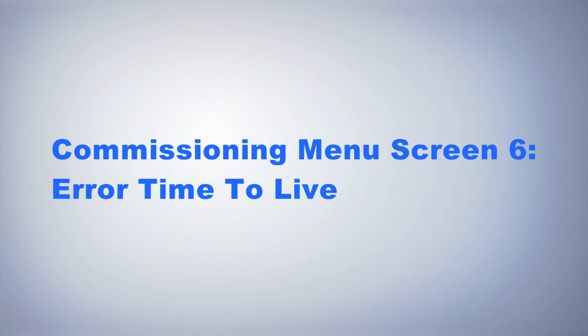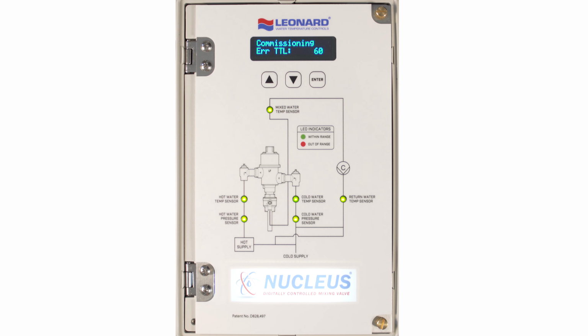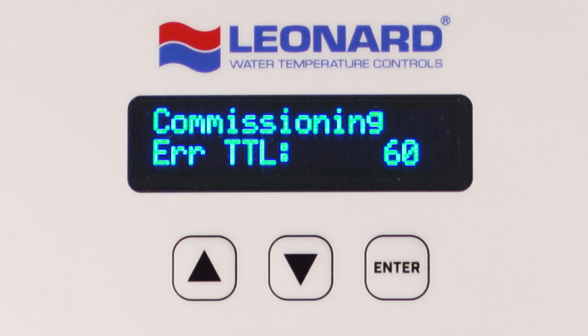Commissioning menu screen 6. Error, time to live. Pressing down 5 times displays error TTL. This indicates time to live, which is a time in seconds and starts as soon as the error time to make live has elapsed. An error that exists past both TTML and TTL will require user recognition to clear error from screen by pressing Enter.